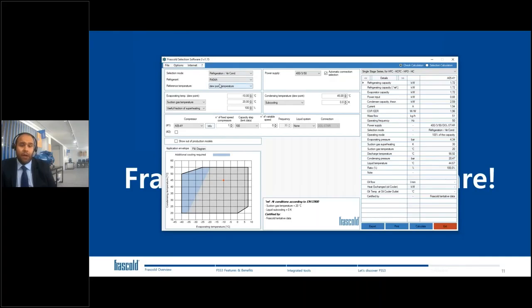Starting from the beginning, we have the selection mode, in which we can set the modality of the system that can be refrigeration and air conditioning or heat pump. This changes only the output, because clearly if you want to design a heat pump, your useful effect is the heating capacity. Otherwise, if you want to design a refrigerating system, your useful effect is the cooling capacity. Then you can choose the refrigerant you prefer. We have a lot of refrigerants, including the newest ones like the HFO blends, like R455A and R454C. And then the reference temperature.